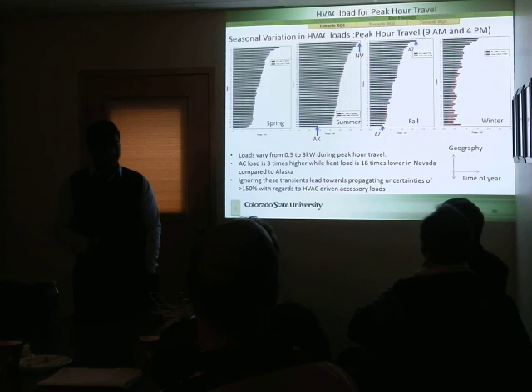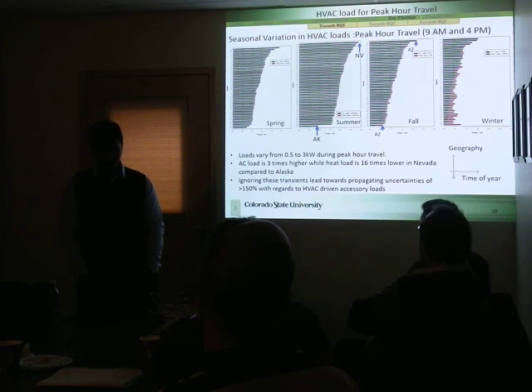Comparing Nevada with Alaska, the maximum AC load during summer in Nevada is about 3 times higher than in Alaska, but during winter, the heat load is 16 times lower. So ignoring these transients while designing HVAC systems results in propagating uncertainties greater than 150% regarding thermal comfort loads.